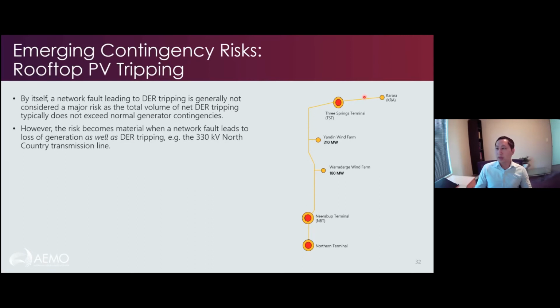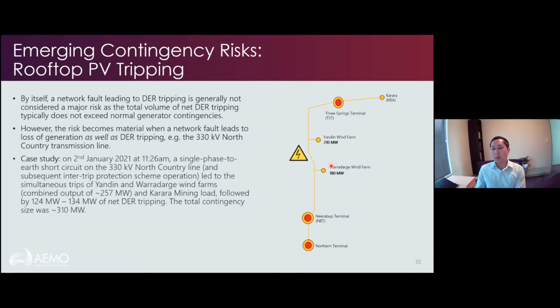So this is the Perth area. This is up towards Geraldton Way. And if that line trips, then you basically lose all of these generators. And the only way this line really does trip, though, is when there's a transmission line fault anywhere along this line. There's a big intertrip. And so this is exactly what happened earlier this year.